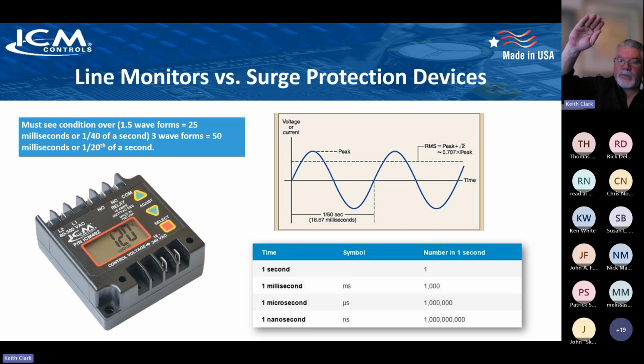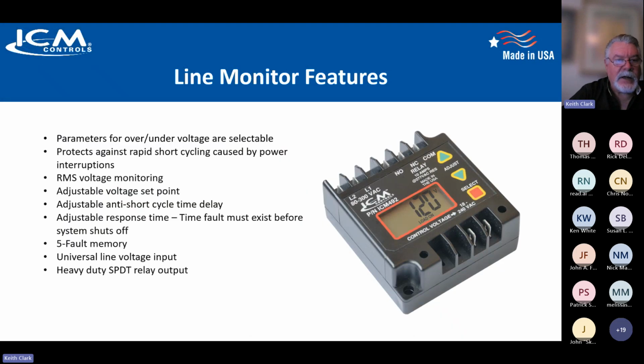So you might have one sine wave that goes a little high, but it might correct itself on the next cycle. Or low, and it might correct itself in the next cycle. So you don't want this thing just dropping out all the time. That's a nuisance. That's going to get you a callback. You want it to interrogate responsibly, make sure that there's actually a problem there before it drops out. And it's a totally different way of looking at and protecting equipment from voltage anomalies. So you set your parameters for over and under voltage.